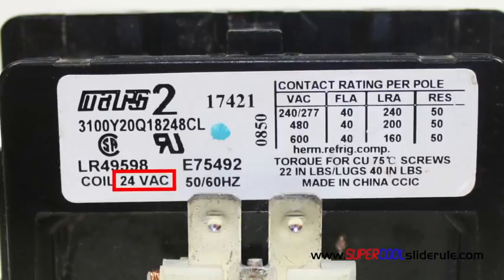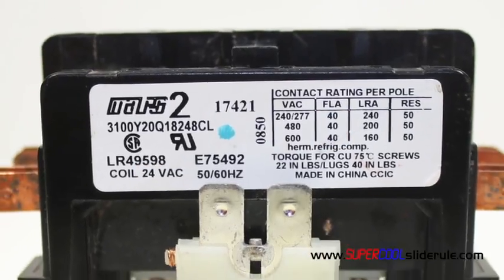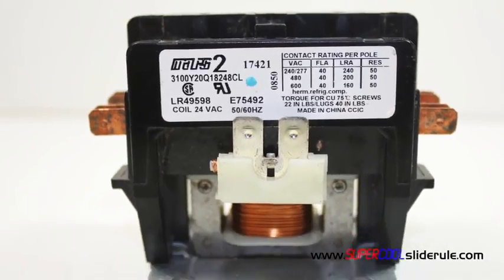Also note the amp rating of this contactor is 40. This lets us know that we should not attempt to feed more than 40 amps through this contactor. Most contactors are available with amp ratings from 25 amps to 50 amps.